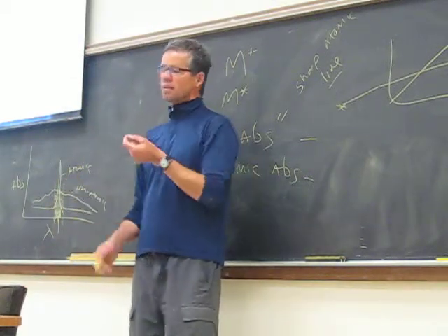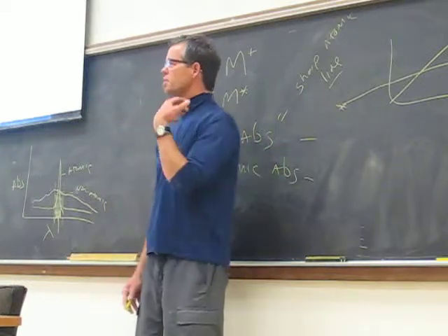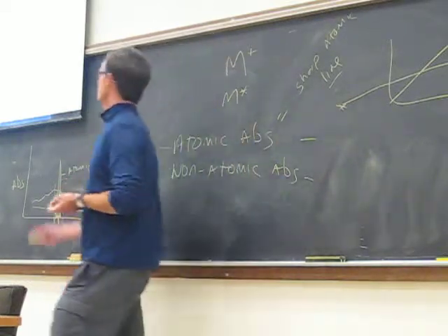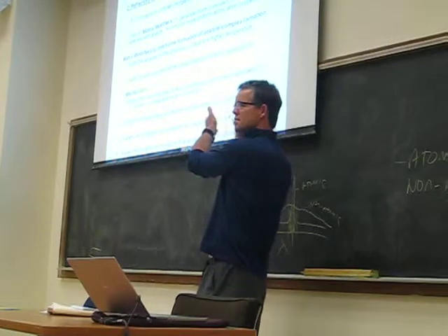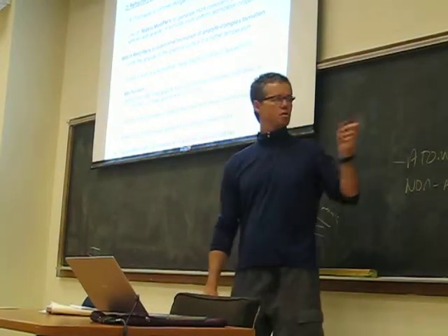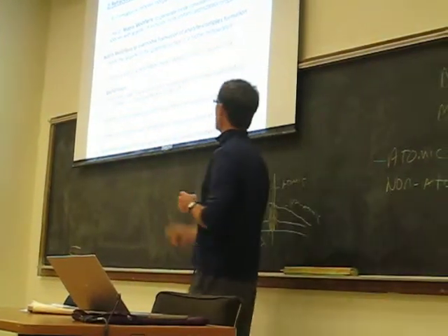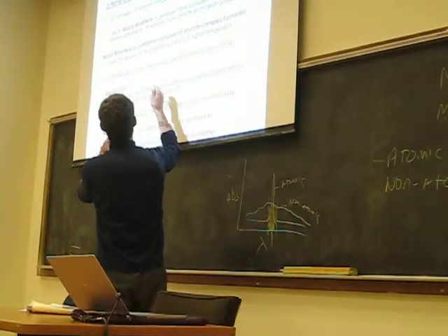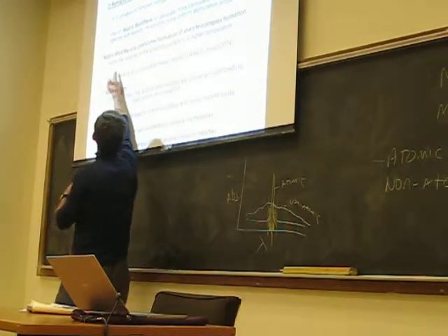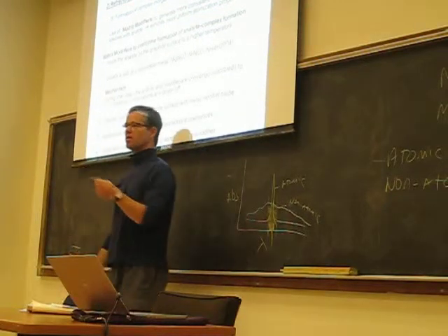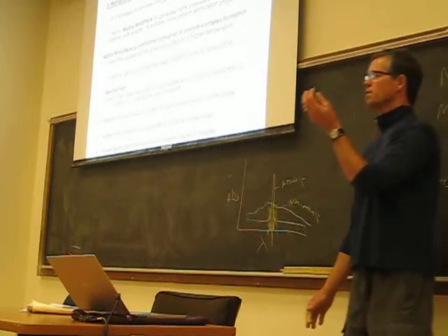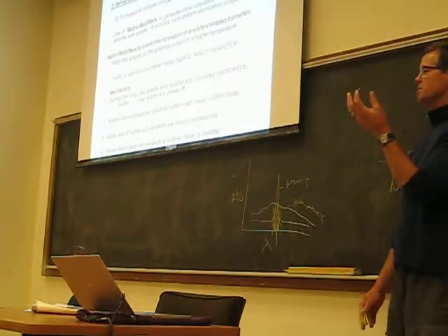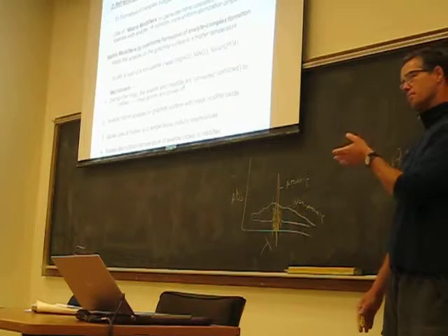You'd say, well, is there a better, more efficient way to do that? And the answer is yes. You'd say, well, I don't know what the levels are, maybe they're low, but I can dilute the samples and dilute the matrix problem out, and I can use a more sensitive instrument, and I can use some other approaches to minimize those matrix issues. And one of those approaches, this is what I'm kind of focused on, is using other kinds of compounds that you can add to the sample. They call those matrix modifiers, in order to change the composition of the sample to help remove the effects that these matrix issues are having on the sample.